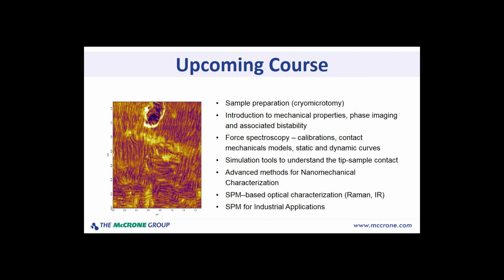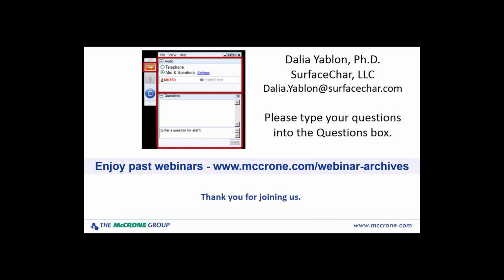In order to get quantitative measurements of modulus, you have to work really, really hard. It is not an easy measurement to get quantitatively accurate. You need to work hard on the calibrations. You need to have a really good understanding of your tip sample dynamics and your indentation depth to make sure you are working within the range that this measurement is accurate. And I would say even then, maybe within 10% after you've worked really, really hard and spent a lot of time on your sample.